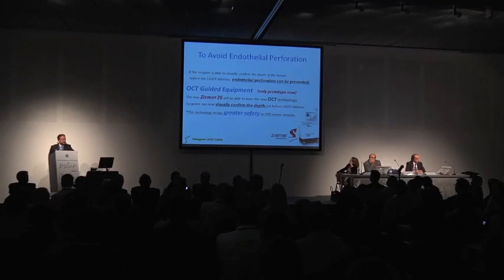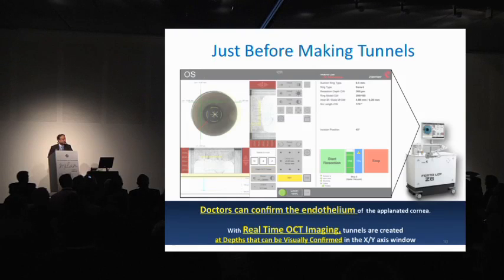OCT-guided equipment, only a prototype now. With the new Ziemer Z6, we were able to incorporate new OCT technology. The surgeon can now visually confirm the depths just before the laser ablations. This technology brings greater safety to ICRS channel creation. You can see the OCT system here — we can see the green light showing the planned tunnel place. The surgeon can confirm the endothelial layers of the cornea.